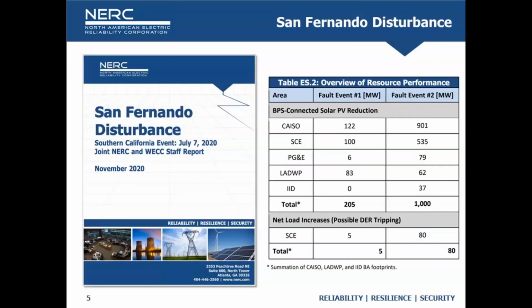While we see things like momentary cessation continuing to show up in disturbances, each of the tripping mechanisms causing solar resources to trip offline unexpectedly are different. Blue Cut fire was erroneous tripping on calculated frequency. Canyon 2 fire was mainly transient AC overvoltage. Palmdale Roost Fire and Angeles Forest Fire were similar to that. And the San Fernando event saw AC overcurrent tripping, DC low voltage tripping, and in all of these, some PLL loss of synchronism and DC reverse current type issues.